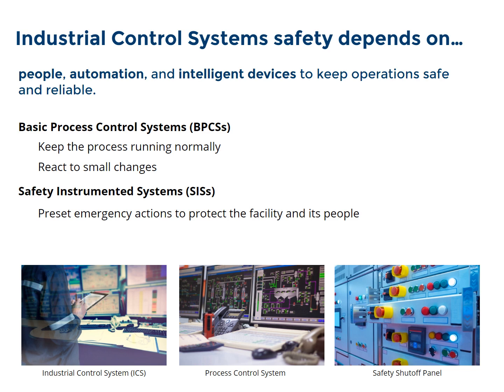Safety instrumented systems, or SIS, are independent safety systems pre-programmed to immediately react when a monitored physical process strays beyond preset bounds. They are programmed to bring the physical process back to a safe state, avoiding a catastrophic event and allowing the operator to attend to the problem and make repairs. When an SIS fails to do its job, we have unpleasant events like the Deepwater Horizon disaster, where the SIS failed to bring the drilling operation back to a safe state, causing months of ecological damage in the Gulf of Mexico.